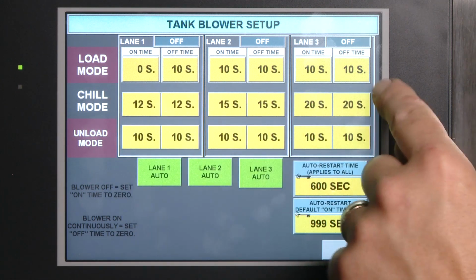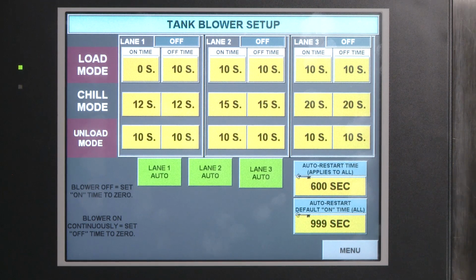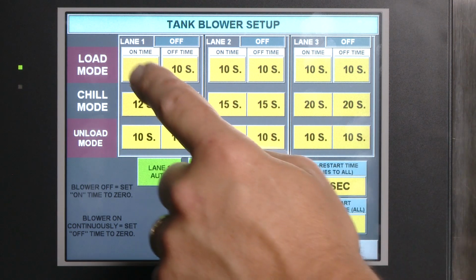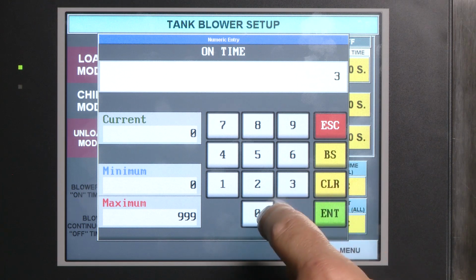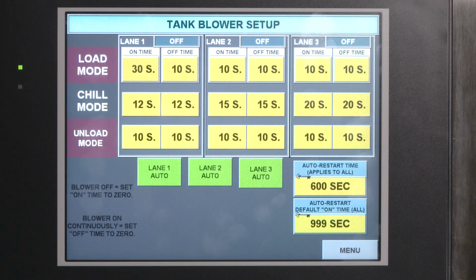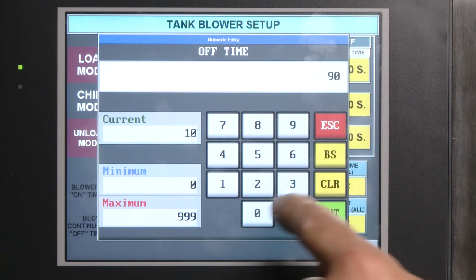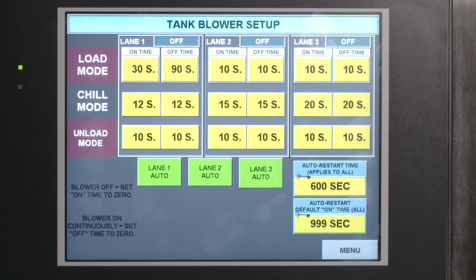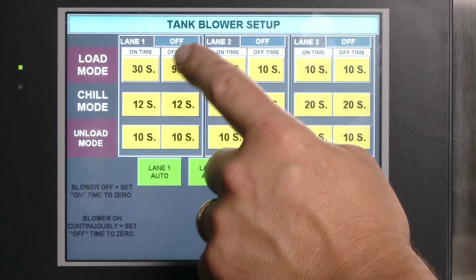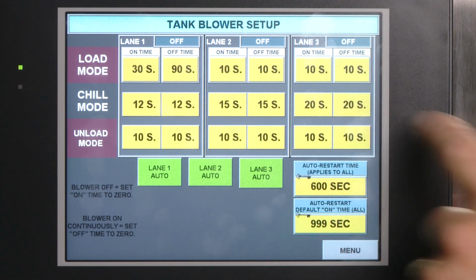The blower's timed mode allows the blower to cycle on and off for intermittent operation. The blower on interval is how long the blower runs when it comes on. For example, if the on time is set to 30 seconds, the blower would run 30 seconds and then shut off for the off time, or 90 seconds. The blower off interval is how long the blower will be off before it restarts.